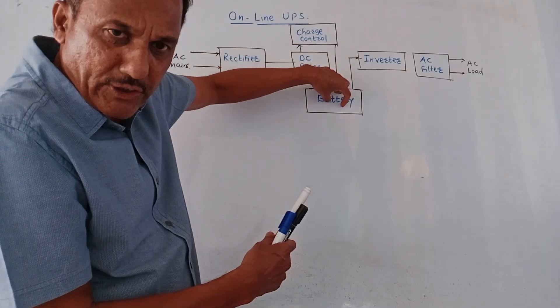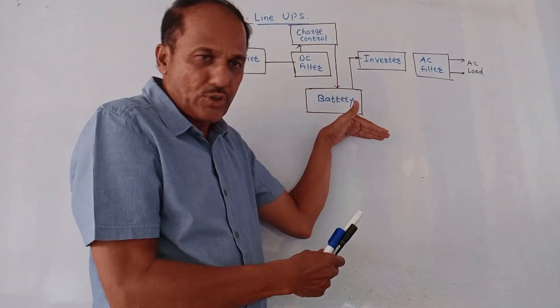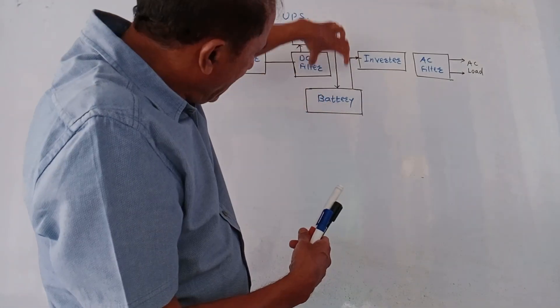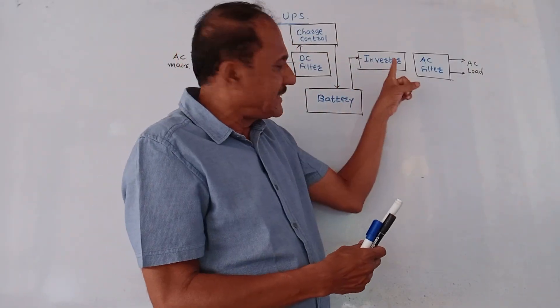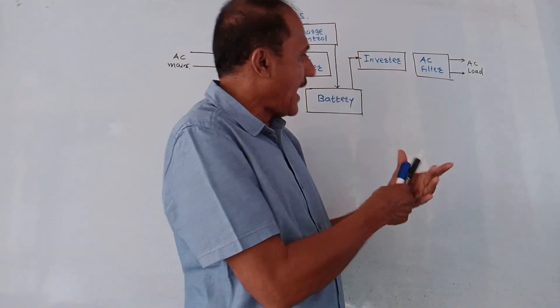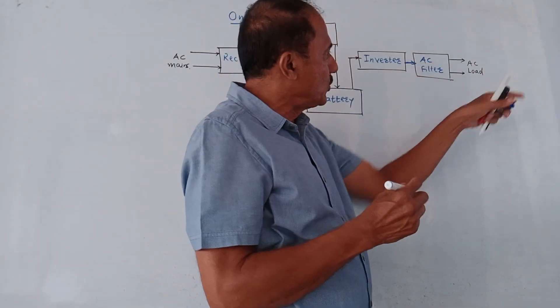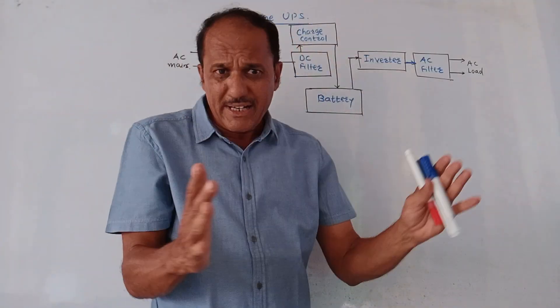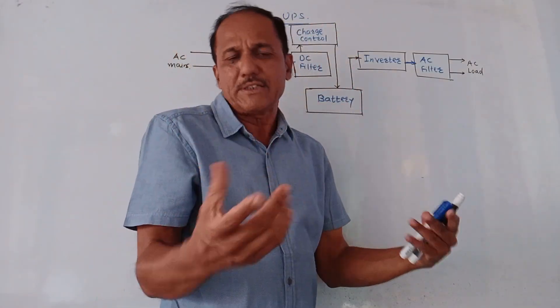At the same time, while the battery is charging, the output of the battery is given to the inverter — to convert the DC signal back into AC. The output of the inverter is applied to the AC filter and then given to the AC load. This is the normal mode of operation, where the mains is always connected and charging also takes place in parallel.